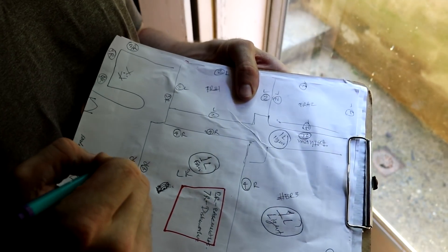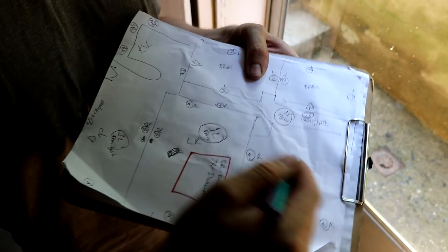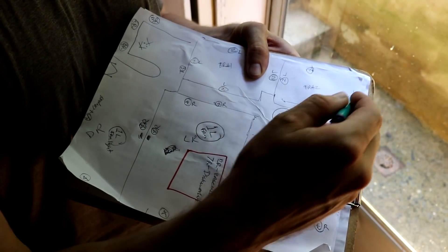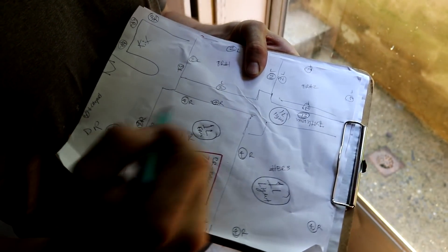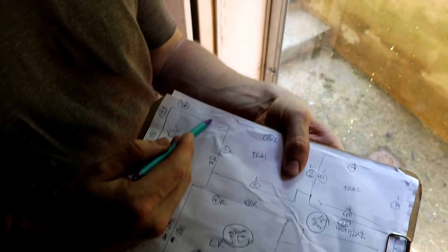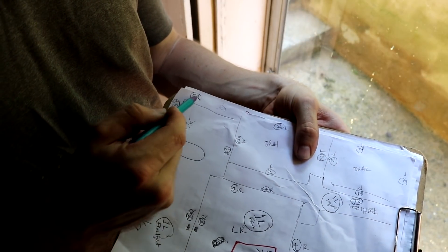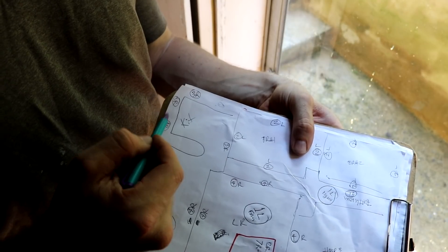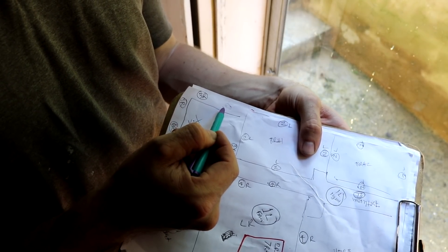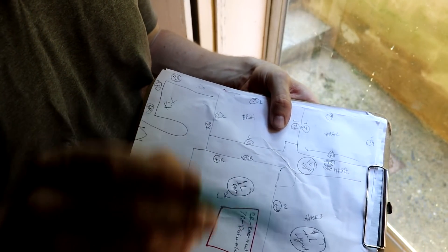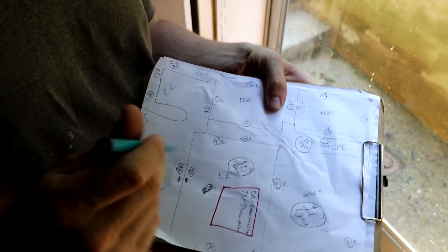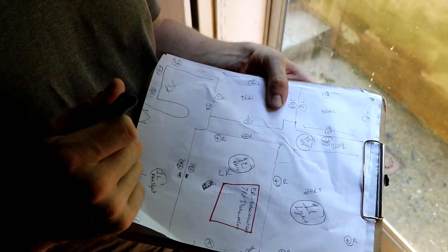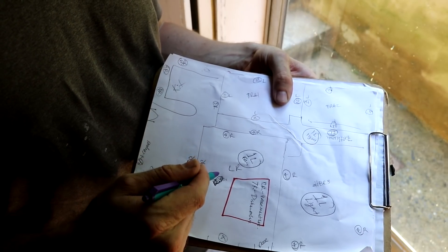And the best thing you want to do though is if anything, it doesn't always make sense. There could be some random outlet that someone tied into this. So unless I have already identified an outlet that goes to another breaker, I will check other outlets. For example, this one here in the kitchen above the counter, that one does, for whatever reason, all these outlets that go around the kitchen, that one didn't go off. My guess is there's a problem with the outlet. That wire has probably come loose inside the box. So I'm going to open that up and check it. But if you have some random outlets here and there, or lights on the outside of the house, or outlets on the outside of the house that you haven't already detected, you'll want to go ahead and check those too. Or any lights in closets, you can check those as well. So that is how I identify things.